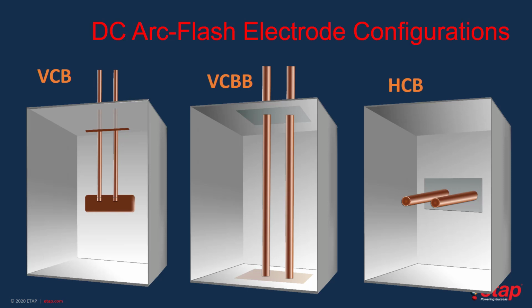For photovoltaic systems, the vertical conductor in a box and vertical conductor in a box terminating in an insulating barrier configurations are likely. In particular, the VCBB configuration is very likely, as shown in the middle image in this slide, and it is very likely to occur in tightly packed conductor areas or where the conductors run very near to the enclosure wall, such as in combiner or recombiner boxes. In fact, there are differences in the results when the enclosure itself serves as a path for current return. This was proven in several of the photovoltaic tests performed by these organizations.